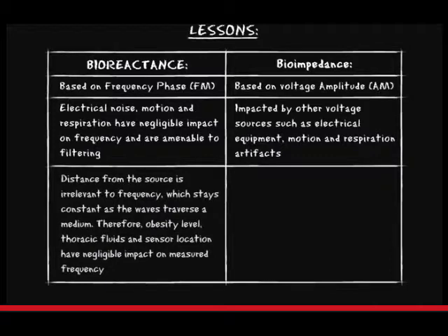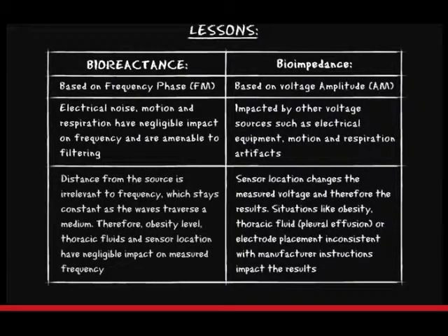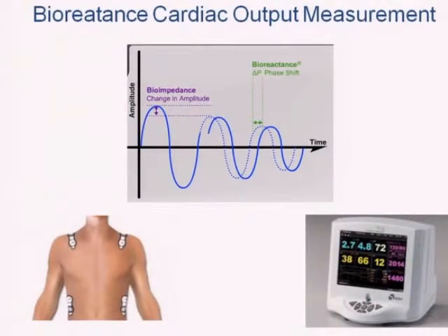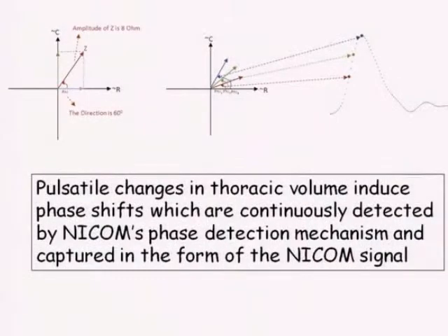As a result, NICOM sensor placement does not have to be exact, and measurements remain accurate despite body size, obesity, and edema. Bioimpedance sensors require accurate placement, and measurements are affected by obesity and thoracic fluid content. So what about bioreactance? So this differs from bioimpedance. With bioreactance, you have electrodes which emit an electrical signal. You then have electrodes which receive the signal. With bioimpedance, one looks at the change in amplitude. With bioreactance, one looks at the phase shift. So that's the way the direction of the electrical signal changes.